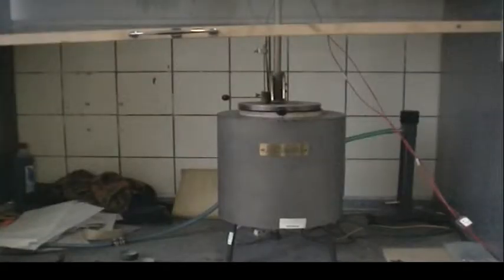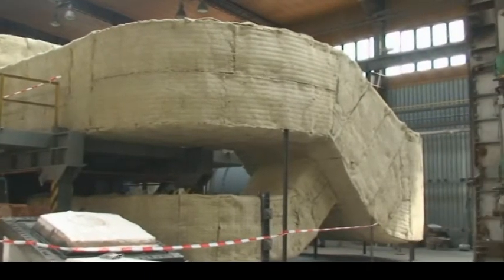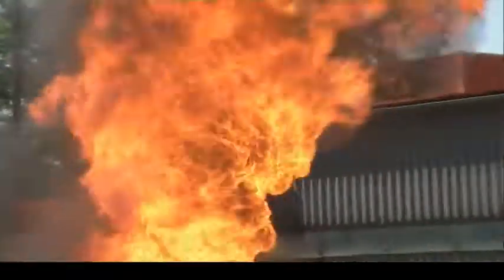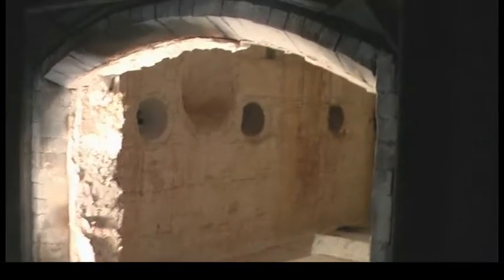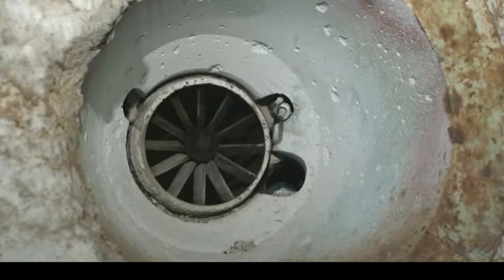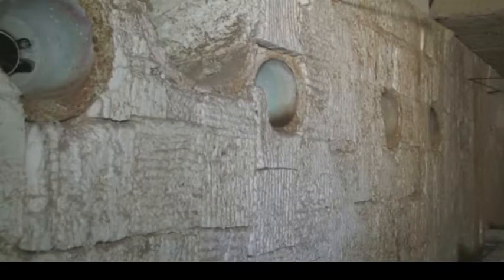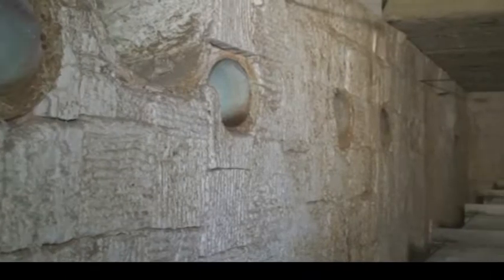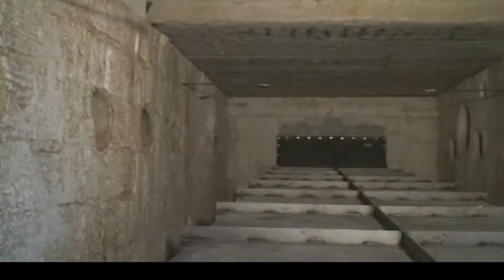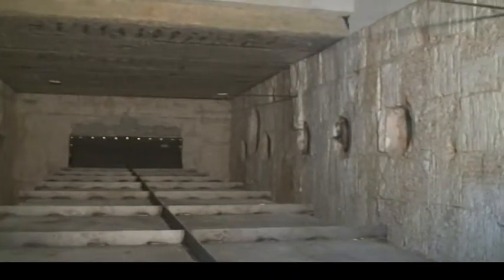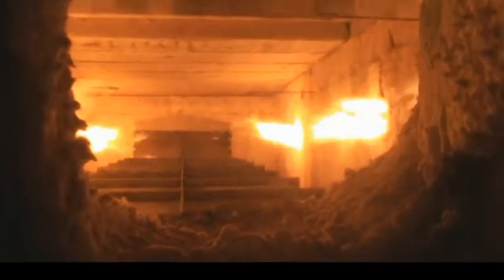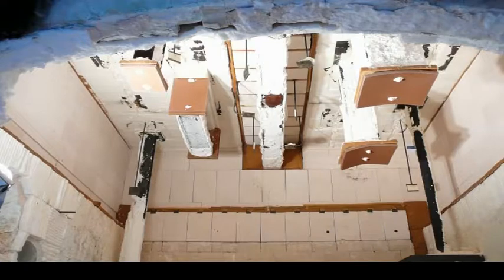The PAVOS Fire Laboratory manages a considerable scope of mostly unique testing equipment and methods intended for testing passive but also active fire protection. For fire resistance tests of construction products and building elements, we have 7 testing furnaces altogether, the parameters of which comply with European standards requirements. For example, the horizontal furnace allows testing of specimens up to 9 meters long. The number of specimens that can be installed into that large space and tested simultaneously in only one test may be considered a customer advantage. This advantage is appreciated mainly by the manufacturers of a wide range of fire protection of building constructions, as well as the manufacturers of penetration and joint seals.